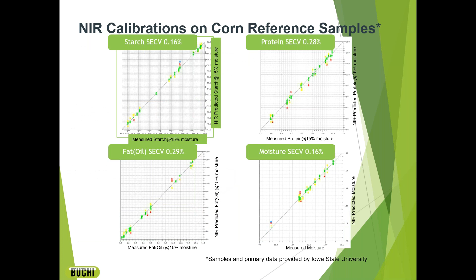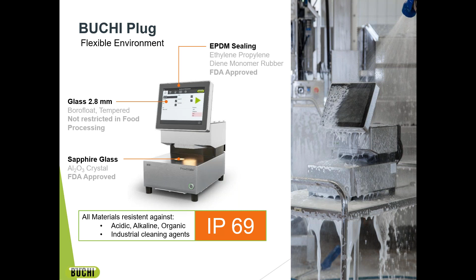Now, appropriate instrumentation plays a very important role in processing. I will highlight the BUCHI Proximate Benchtop NIR spectrometer, a suitable instrument for production environments in a typical ethanol plant. This IP69 rated unit can be washed down during cleaning in place operations with minimal risk to damage. The Proximate has an inbuilt Windows computer and comes with a touchscreen enabled interface protected by an FDA approved EPDM sealing, in addition to the state-of-the-art sapphire glass light window.